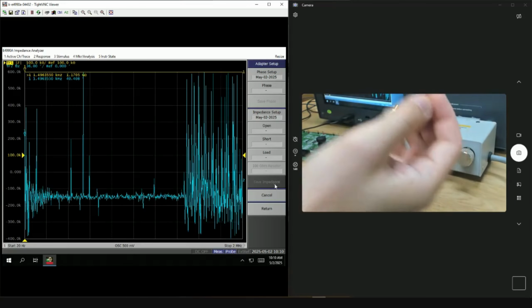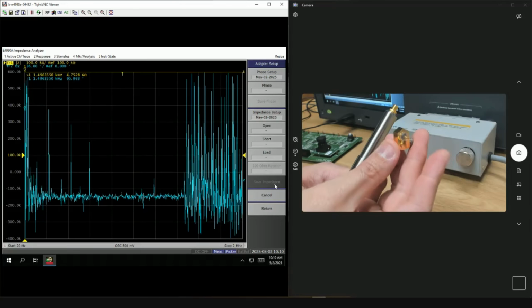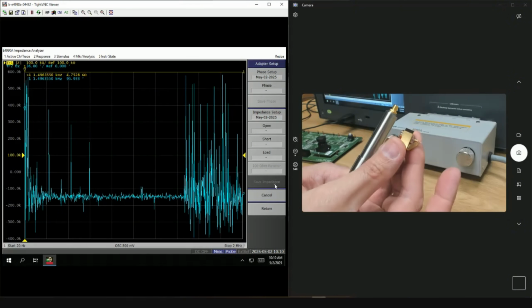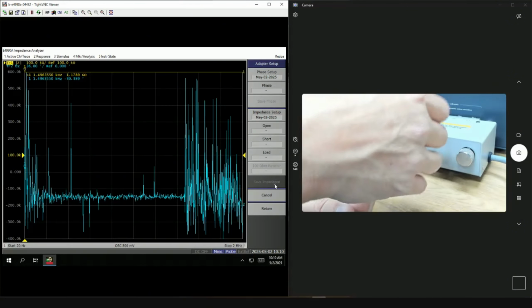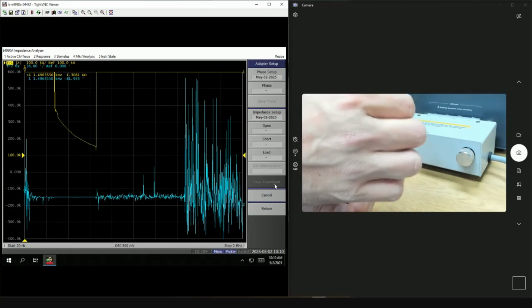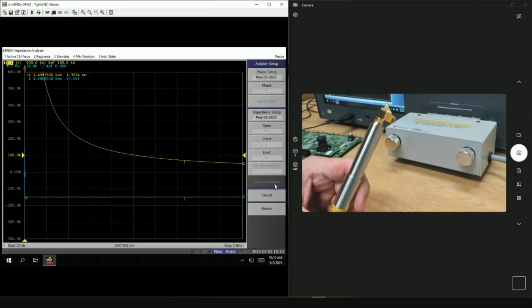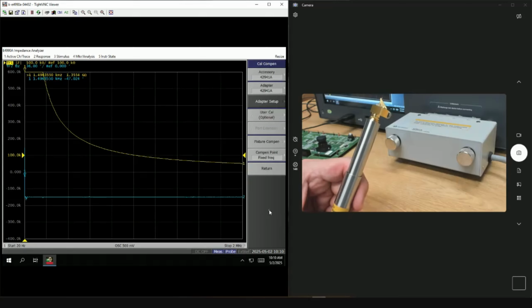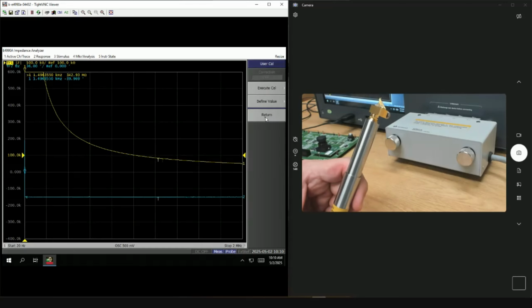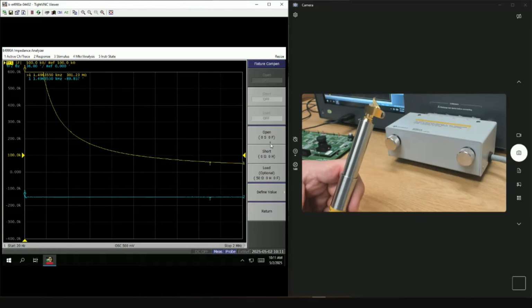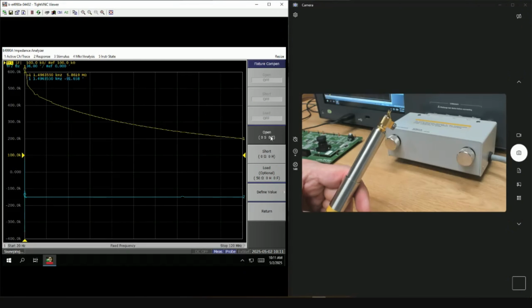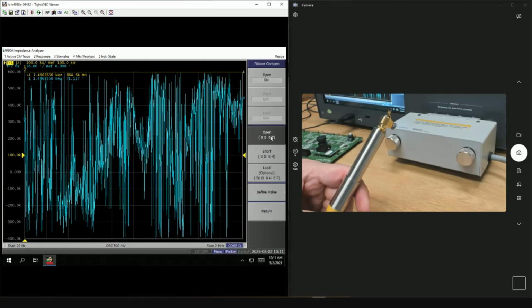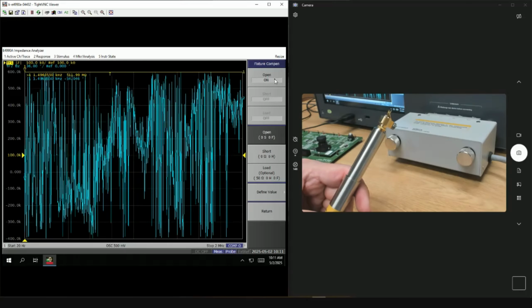So let's say we are using this as an extension from what we have calibrated. We have to run another round of quote-unquote calibrations to compensate for the additional probe head here. So the next thing you do is go back to return, then user cal. This one, sorry, is fixture compensation. It's under here. Right now my probe is open, so just click open and start measurement. When it's done, this will become on.